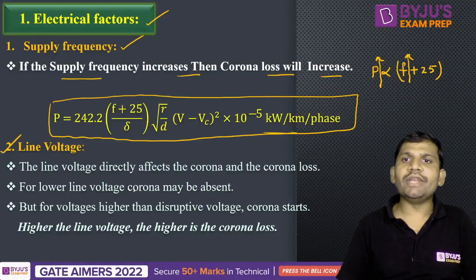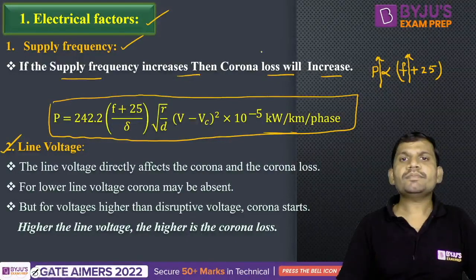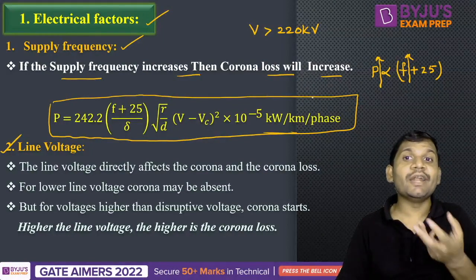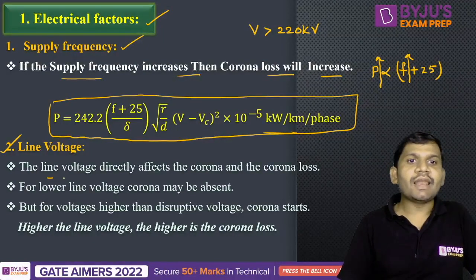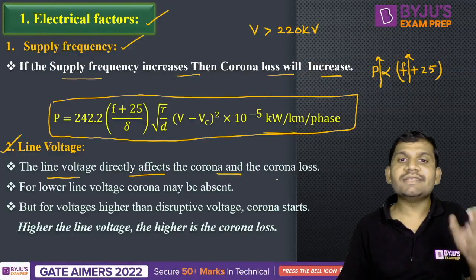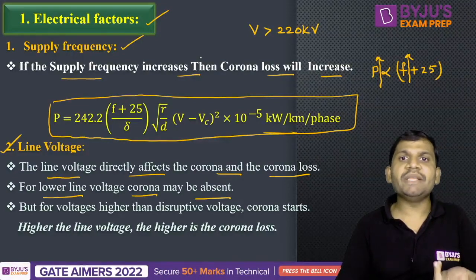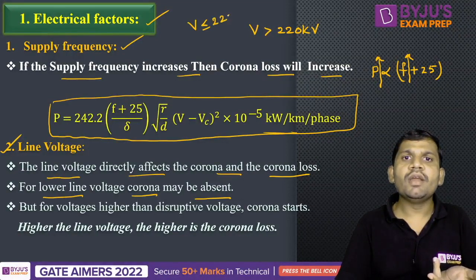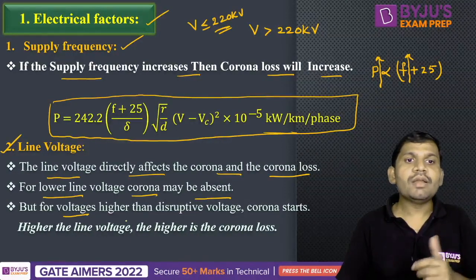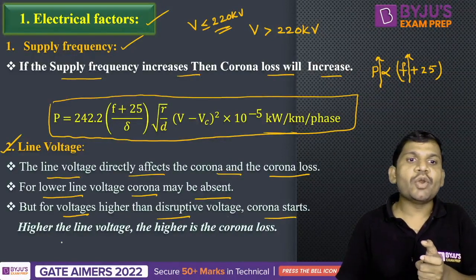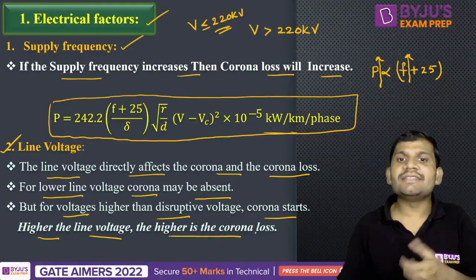One more factor is line voltage. For voltage greater than 220 kV only, we can consider the corona effect. The line voltage directly affects the corona loss. For lower line voltages — for V less than 220 kV — we can neglect the corona loss. But for voltage higher than the critical disruptive voltage, corona starts. Higher the line voltage, higher is the corona loss.